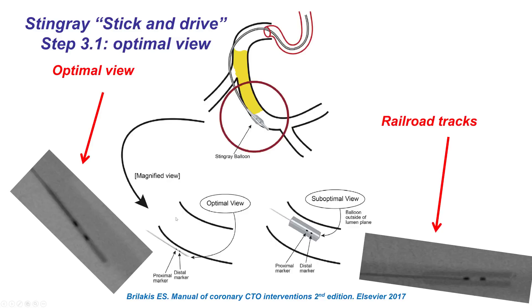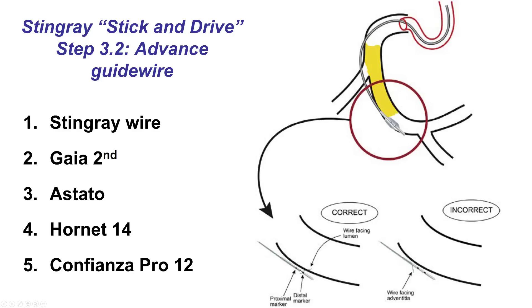Once the optimal view is selected, the next step is to advance a guide wire. In addition to the Stingray wire, several others can be used, such as the Gaia, the Astato, the Hornet, and the Confianza Pro 12.